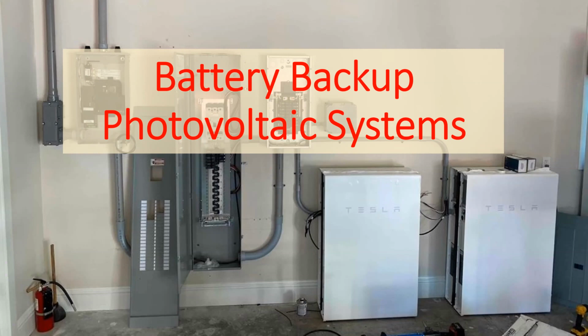Okay, so let's move on and first talk about a couple of things. Battery backup photovoltaic system: we are not talking about off-grid systems here. We're talking about systems that are tied into the utility. But every once in a while, those utilities go down. There's an ice storm or a hurricane or something. You lose power for an hour, a day, or a week, whatever the case may be. A lot of folks, I know up on Long Island, there was a lot of concern over nasty storms this winter. And I know that quite a few natural gas generators went in, and I think a few solar backup systems went in. Here in Florida, we've got lots of battery backup systems in place. And so let's take a look at what they look like, and then we'll see what's inside the box.